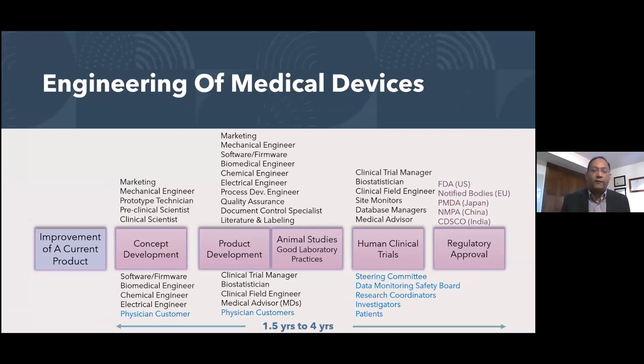But typically in the world of medical devices, you are leveraging your previous information. So the industry is a little bit slow from that standpoint. However, you're not doing three-phase trials, they're single-phase trials, but they can be long. There are a couple of interesting things here. There has to be a defined protocol, and the protocol will have defined success criteria and failure criteria. Those are submitted to the regulatory authority.